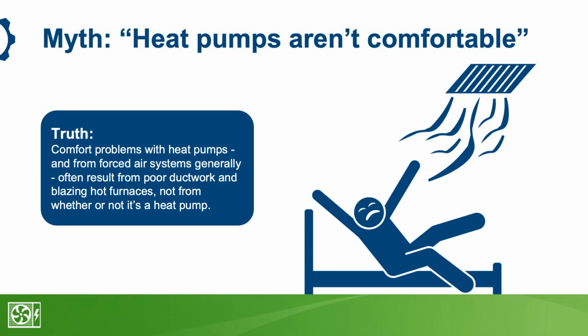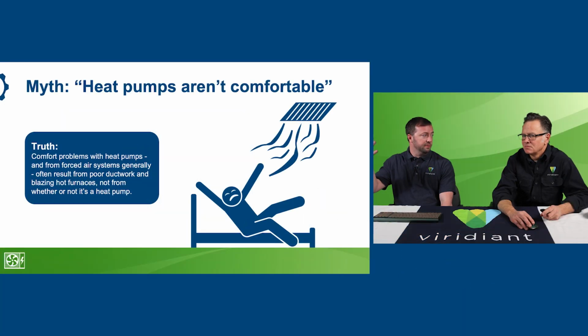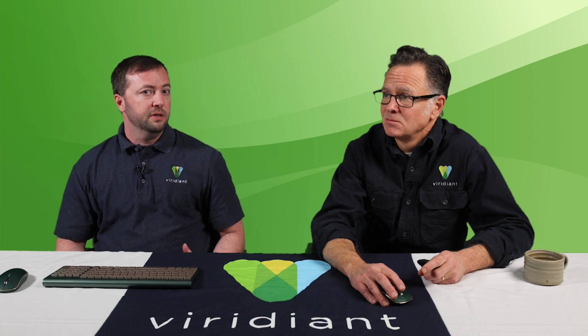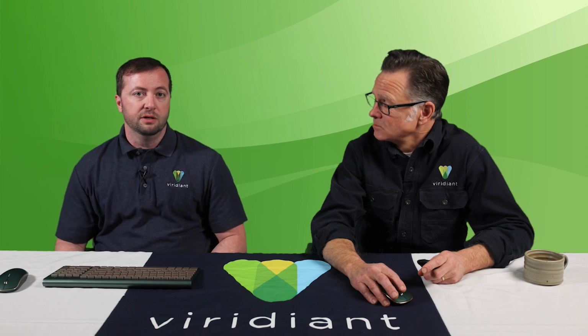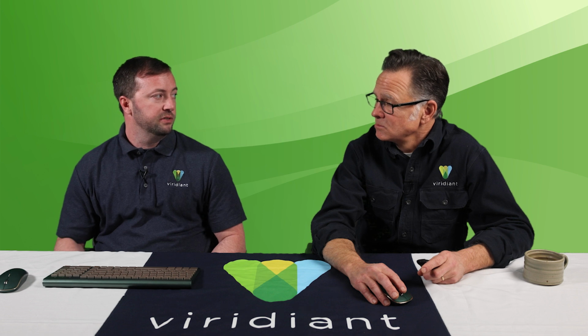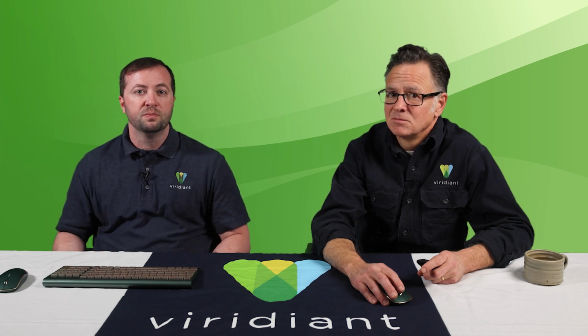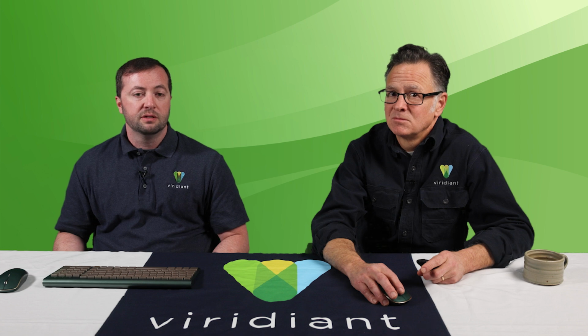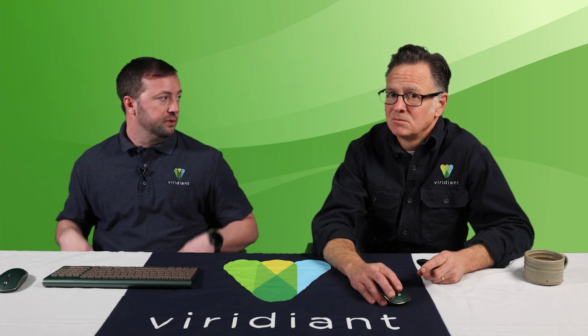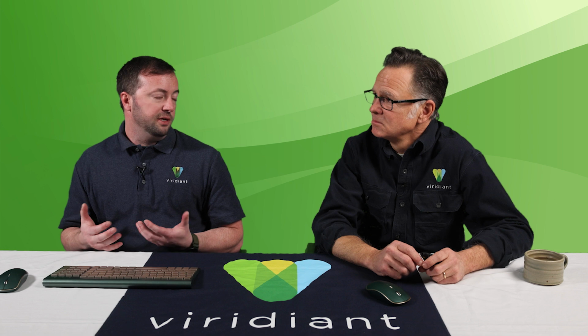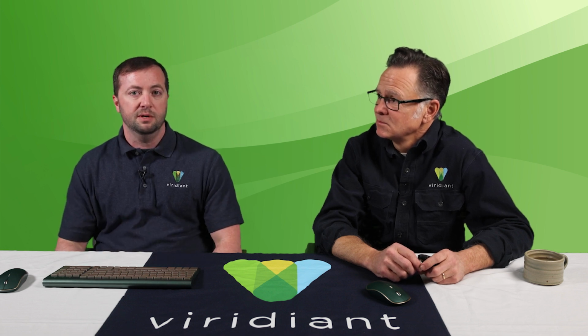One of the other things that can affect comfort is where the supply vents are located. Sometimes those are the real problem. Supplies ideally should be positioned so they're not blowing air directly on the people living in the space. They should just be keeping the room comfortable without the occupants even knowing if it's running or not, because they're not feeling that breeze. So if new ducts are being installed, the supply placement should definitely be considered as part of that installation, and they should be placed so they're not throwing air on the people in the room. If there are supplies already in place, you can get different grills that will direct the air in different directions, again with the goal of keeping it from being blown on the occupants in the space.